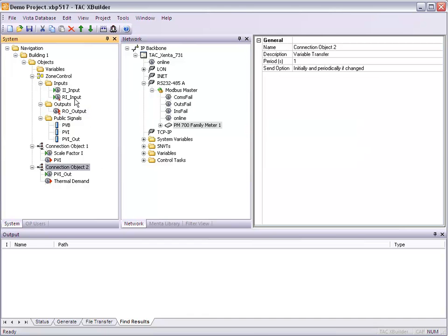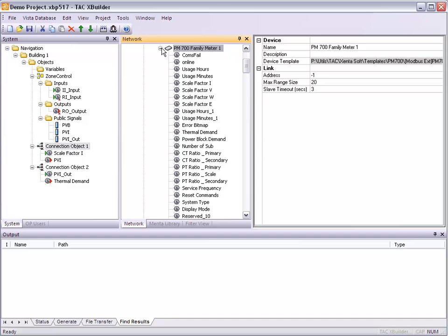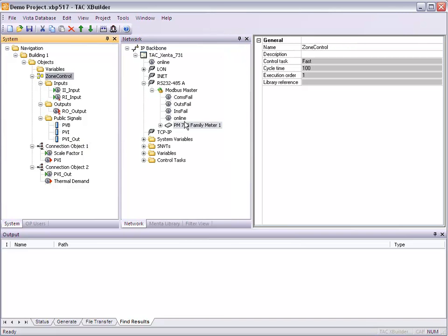If it's from a Menta program to something else, I can do a quick scan and only send if something has changed. If I'm getting data from some other device, Modbus or whatever, I set the period up, at least not lower than 10 seconds, because then I go easy on the bandwidth usage on my Modbus here. So this is about it.